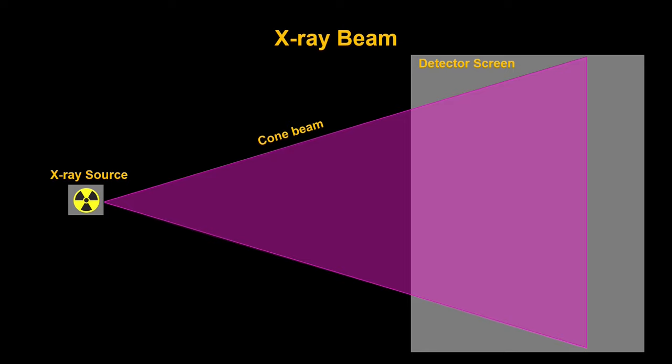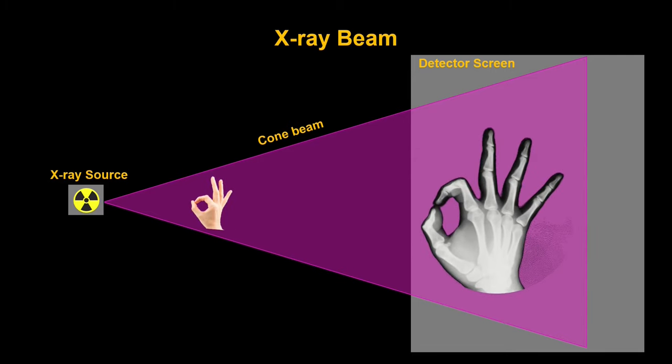There are some interesting consequences of the cone beam geometry that I'd like to highlight. Mainly, if we have a sample between the source and the detector, the image that will appear on the detector is larger than our sample. This is because the X-rays are divergent, and so after they interact with the sample, they're still spreading out before they hit the detector. This magnifies the image of our sample on the detector screen. And when we move the sample closer to the X-ray source, we can magnify the image even further. The opposite is also true. When you move the sample closer to the detector relative to the source, it'll appear smaller. This is just like when you make a shadow with your hand on the wall. The closer you are to the light source, the larger your hand will appear.